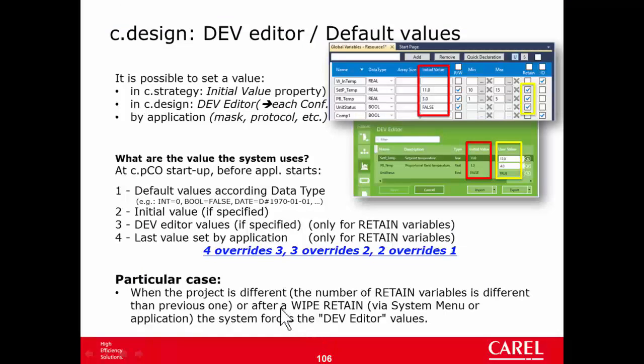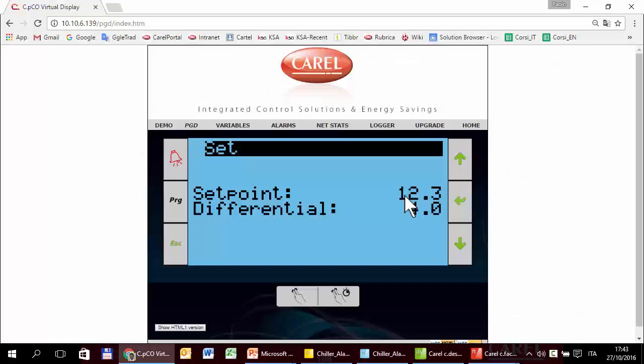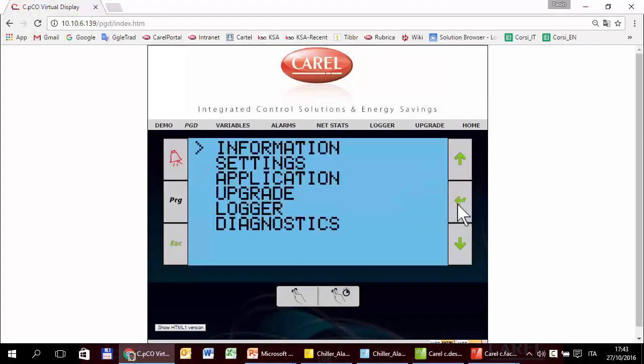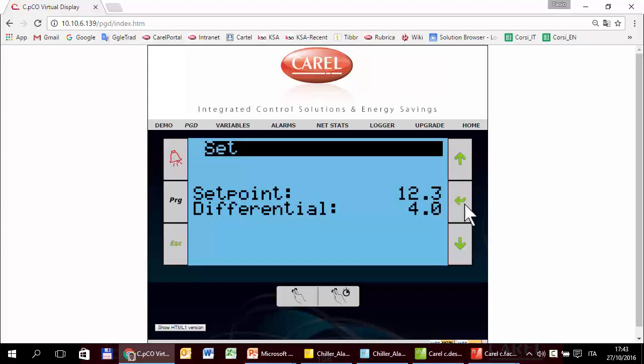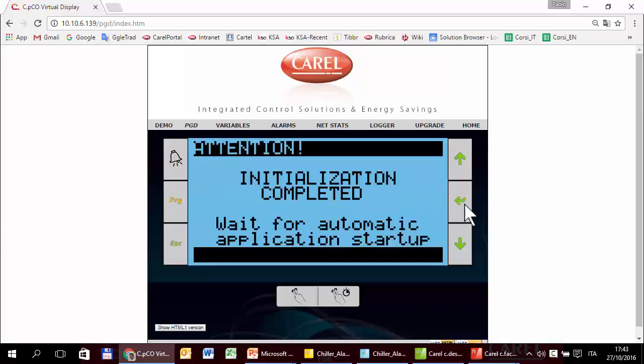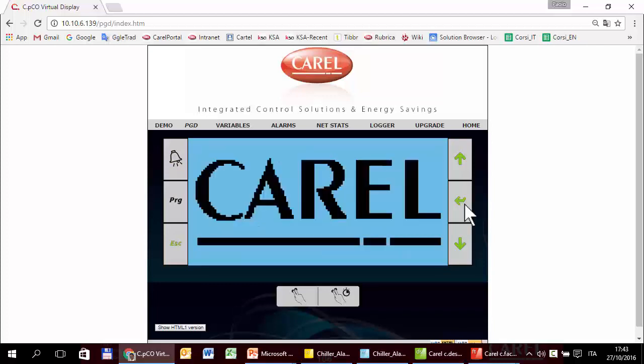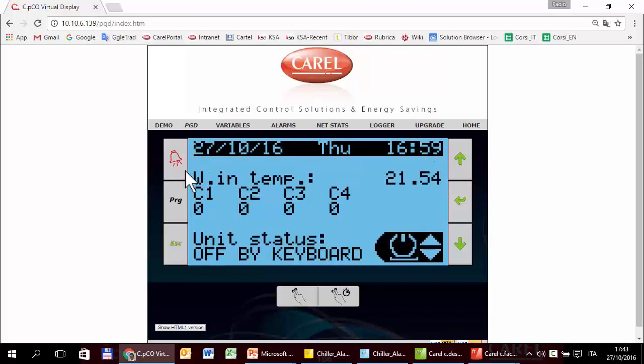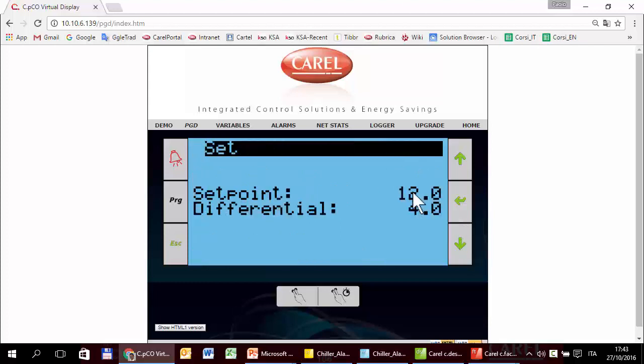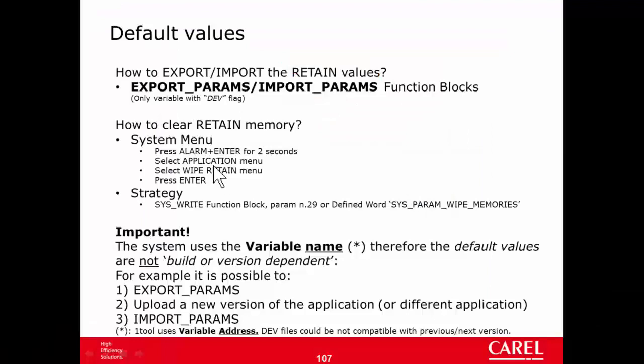Now we can try the wipe retain. Currently the setpoint is 12.3. I will wipe the retain and expect the setpoint to go back to the default value of 12. I enter the system menu, go to Application, then Wipe Retain. Attention — there is no confirmation, so as soon as I press enter it will wipe the retain. The product is restarting, and setpoint is back to 12. So we have tested this part as well.